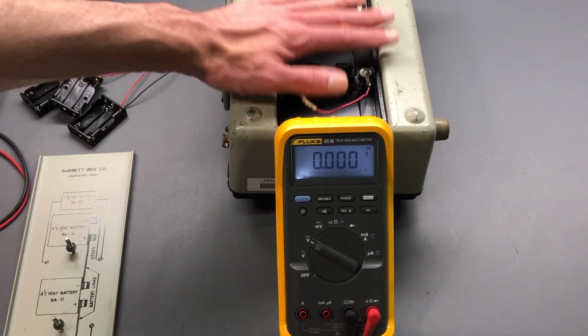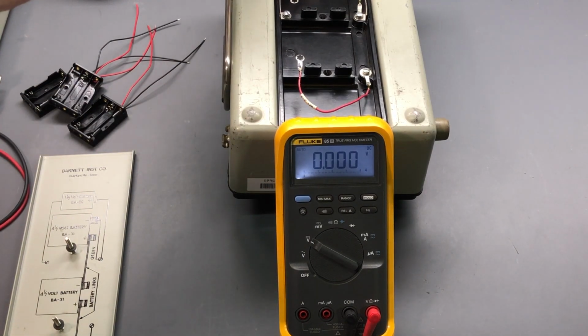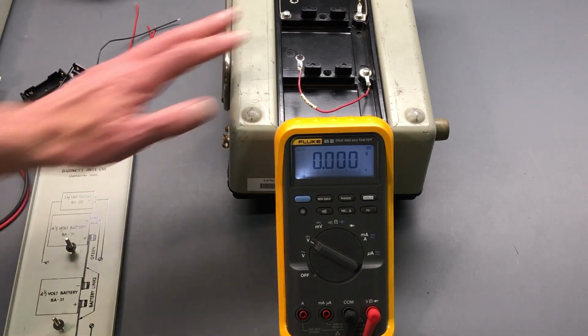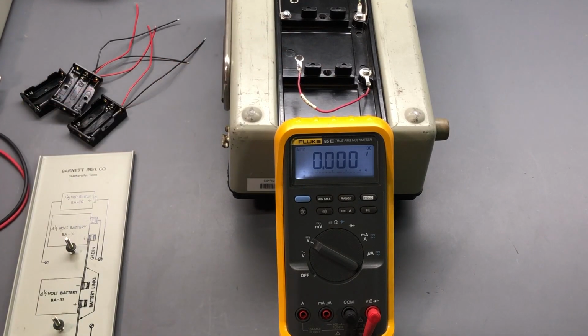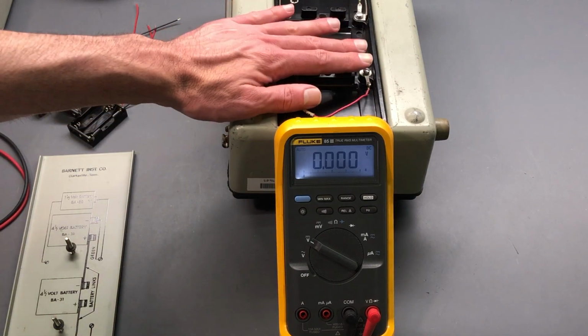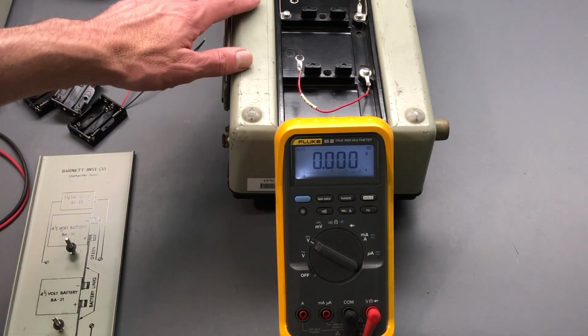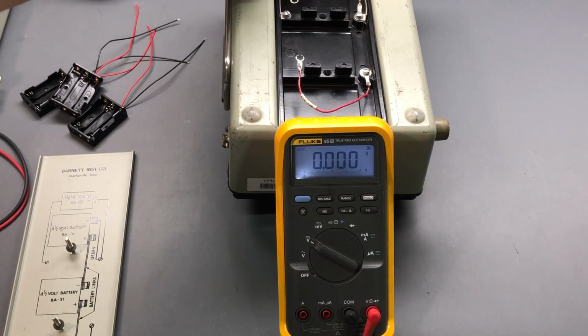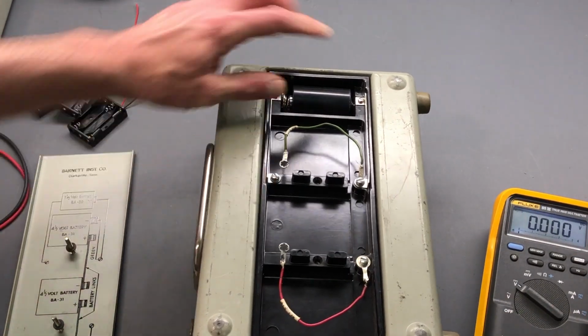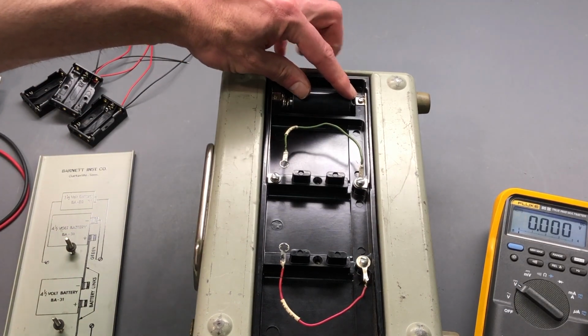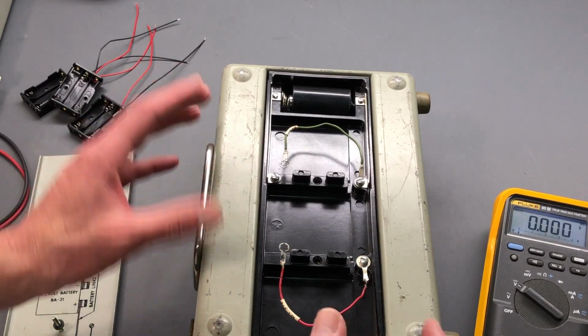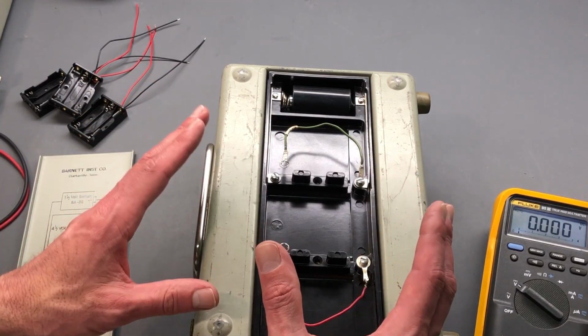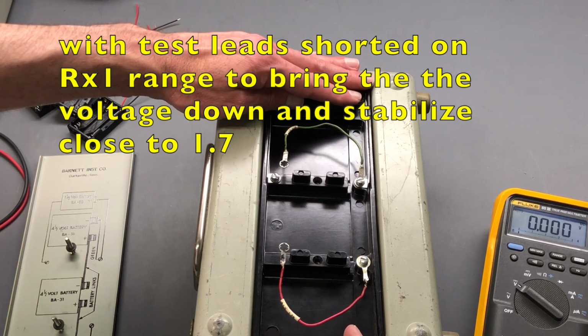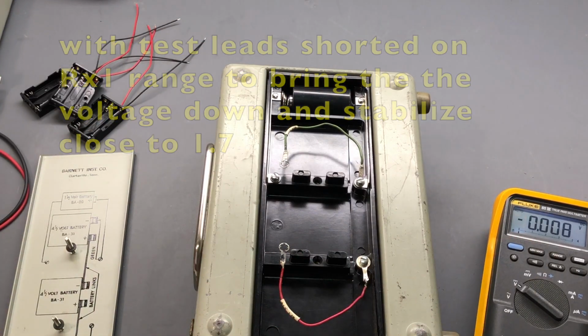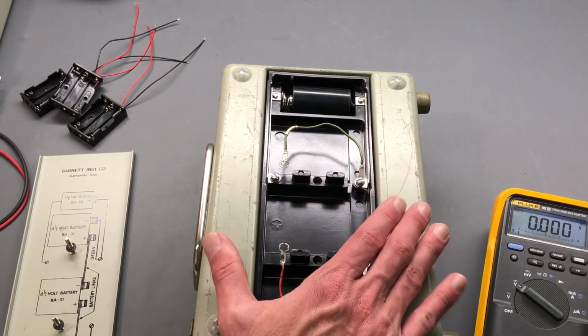And actually, it's that voltage plus this D-cell voltage, which again would be very close to 1.8 when it's new. When you put a little bit of use on the lithium batteries, you'll find that they drop to about 1.7 to 1.6, and they'll stay around that value for a very, very long time, particularly with the low use that this meter has. A brand new lithium AA up here in our D-cell position, move this back over again. When you first install this, 1.8 volts across here, you'll find that the meter doesn't quite zero out. If you give it just a minute or two, that 1.8 volts will drop down to about 1.7, and then the meter will fall within the range that you can actually zero it out.